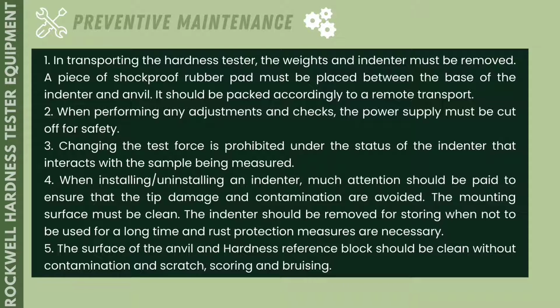Number 4. When installing and uninstalling an indenter, much attention should be paid to ensure that tip damage and contamination are avoided. The mounting surface must be clean. The indenter should be removed for storing when not to be used for a long time, and rust protection measures are necessary. Number 5. The surface of the anvil and hardness reference block should be clean without contamination, scratch, scoring, and bruising. And coating of rust protection oil is necessary when installed.